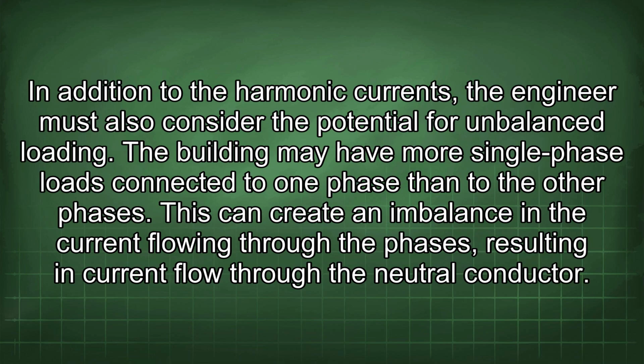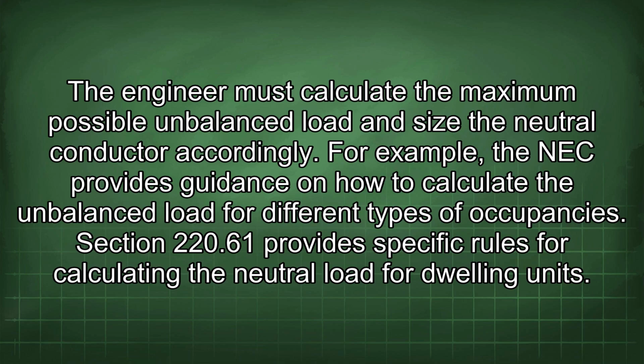In addition to the harmonic currents, the engineer must also consider the potential for unbalanced loading. The building may have more single-phase loads connected to one phase than to the other phases. This can create an imbalance in the current flowing through the phases, resulting in current flow through the neutral conductor. The engineer must calculate the maximum possible unbalanced load and size the neutral conductor accordingly. For example, the NEC provides guidance on how to calculate the unbalanced load for different types of occupancies.